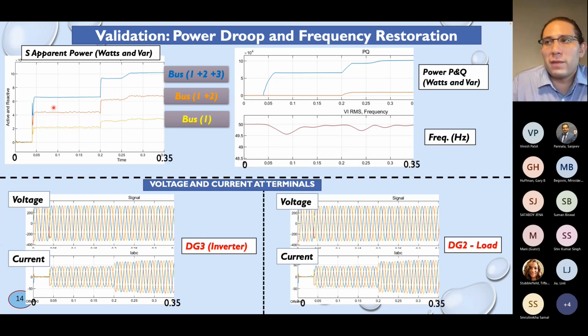So here I'm showing the apparent power on the y-axis, and on the x-axis I have the time in seconds. So here we can see the operation of bus one when it's feeding the load. We can see what happens now when we feed the load controlled by two different buses, like bus one and bus two I showed before, which is in orange, and we can see an increase in the step. And in the third step, when we feed it with the three of them, we can see how we are actually completely feeding the load demand from the whole microgrid.